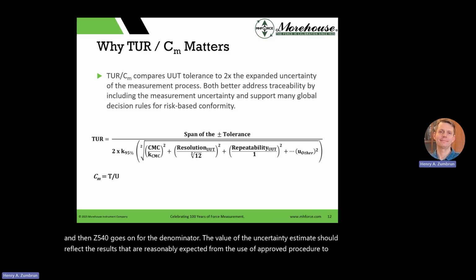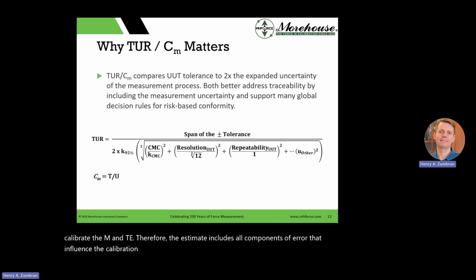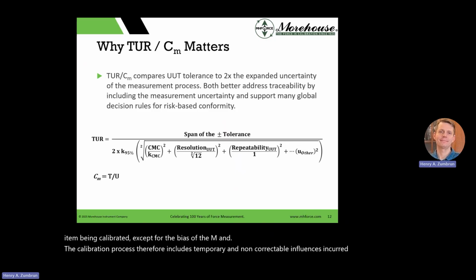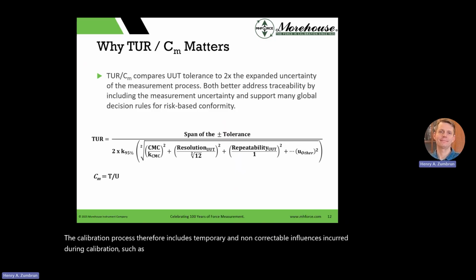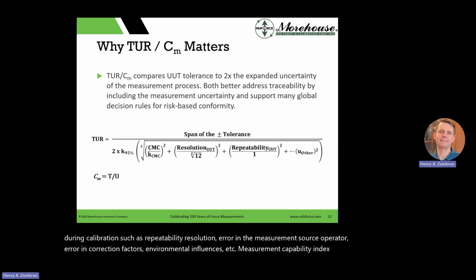M&TE. Therefore, the estimate includes all components of error that influence the calibration measurement result, which would also include the influence of the item being calibrated, except for the bias of the M&TE. The calibration process therefore includes temporary and non-correctable influences incurred during calibration, such as repeatability, resolution, error in the measurement source, operator error in correction factors, environmental influences, etc. Measurement capability index is a metric used in metrology to evaluate how well a measurement process or system can meet specified tolerance relative to the measurement uncertainty.